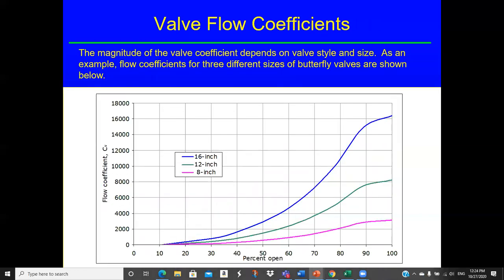Here's some more. I believe these are butterfly valves. And you see you have to get the curve for not only the model number, but the size of valve that you have. So these show 3 different diameters: an 8-inch, 12-inch, and 16-inch valve. And so you can see the variation as we start to pinch that handle down, or pinch the valve shut. It's certainly not very linear over the entire flow range. That's why you need to get the curve.